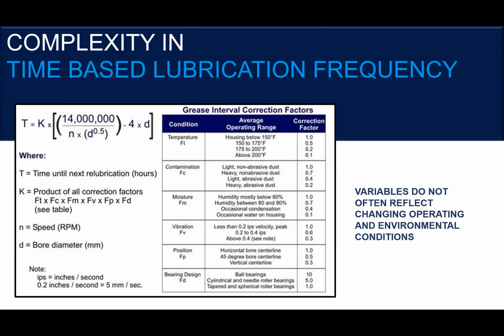So this happens to be one calculation. There are many calculators out there, often resulting in somewhat similar numbers. But look at the complexity of these formulas, even just something as simple as speed. How many of us have motors that don't operate at a constant speed? And I think that number is only going to increase over time, as people redesign process control for energy optimization, moving away from control valves toward variable frequency drives and variable speed drives, which have different operating speeds.